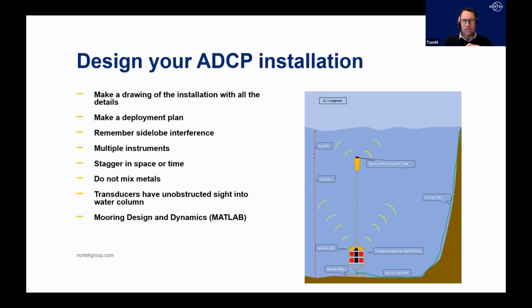Other things we see, especially with profilers, is that people are forgetting side lobe interference. Because of the surface, when the instrument is hitting the surface, we have side lobe problems. And that's something you have to remember, and don't use the data close to the surface.